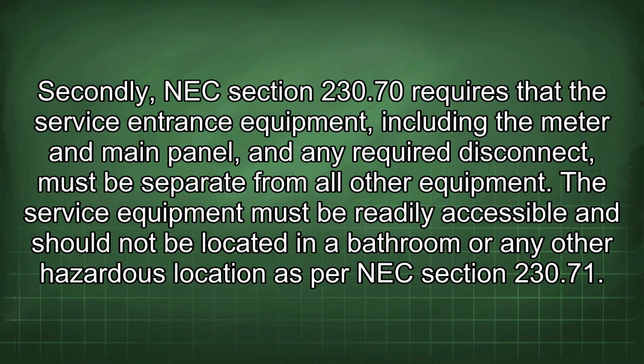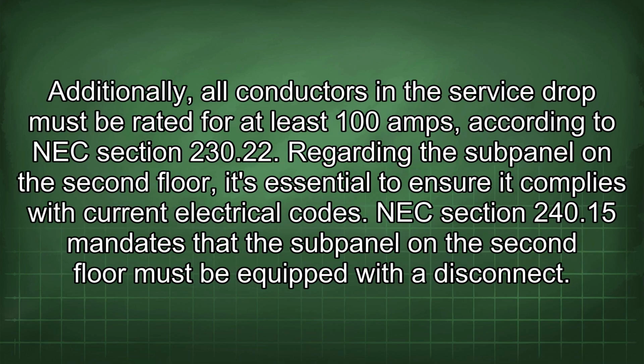The service equipment must be readily accessible and should not be located in a bathroom or any other hazardous location as per NEC Section 230.71. Additionally, all conductors in the service drop must be rated for at least 100 amps, according to NEC Section 230.22. Regarding the subpanel on the second floor, it's essential to ensure it complies with current electrical codes.